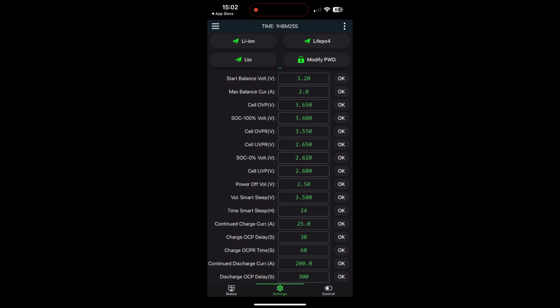But what will happen is when you're charging up, it'll hit 3.6. The SOC 100% will not allow any current to go into the cells to charge them. However, it'll still allow current to come out, so you'll still be able to discharge your pack. However, you won't be able to charge the pack until it hits the cell OVPR, the cell over voltage protect reset. So once all of the cells come below 3.55 volts, the BMS will allow charge to start going back into the cells. Okay. All right. Moving on.